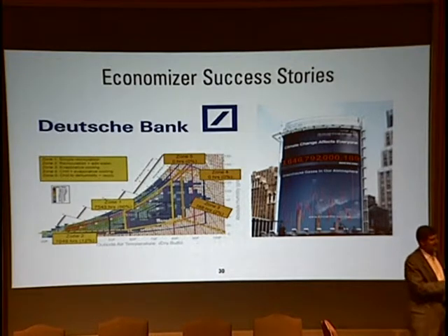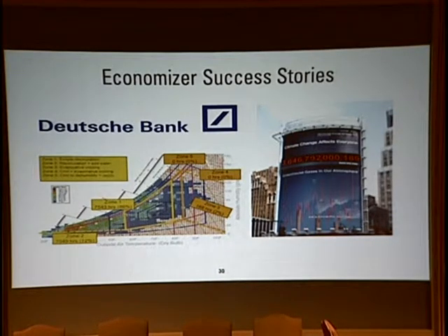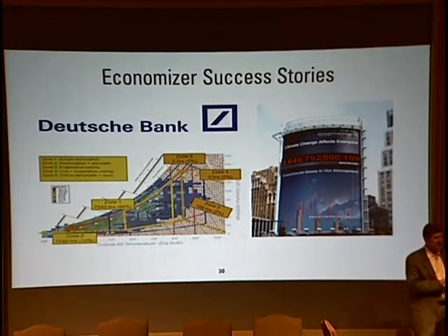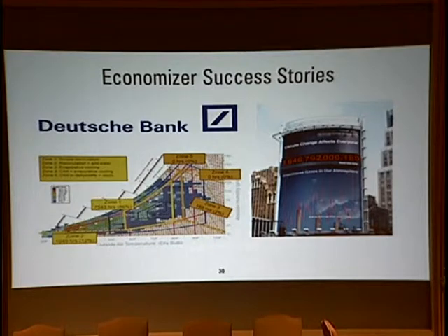So this is not an internet superstar. This is not somebody that is risk accepting, right? Andrew talked his bank into letting him run free cooling because of the significant economic benefit that he would get by doing it. And he's able to show them that I don't need the mechanical chilling.